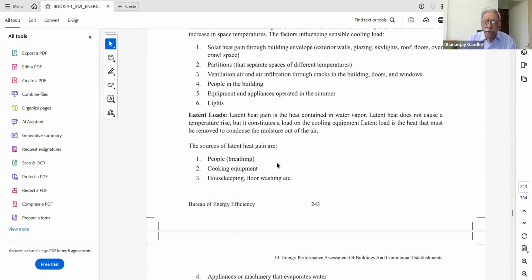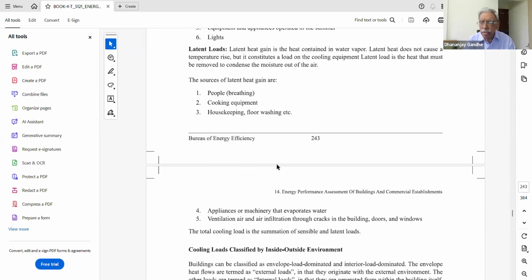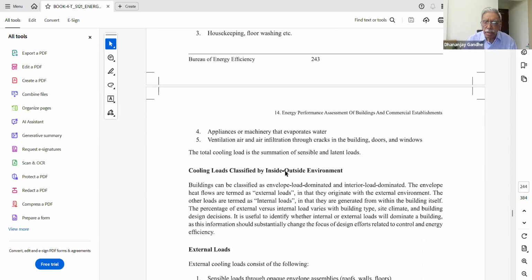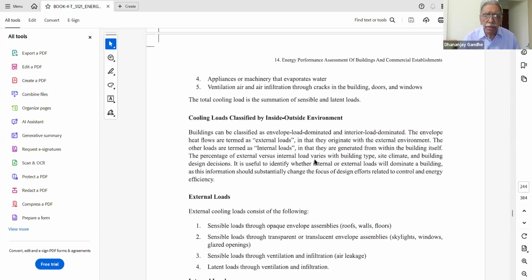The latent heat consists of, again, people: when they breathe, they inhale air, and they also exhale air. So through exhaled air, our breath, when we breathe out, you see the breath is always hot. It is going to add to the heating load. Cooking equipment, housekeeping, floor washing, etc., some operations also contribute to that. Plus, in addition, of course, if you have, let's say, a coffee maker or you're boiling water, the water vapor that goes into the atmosphere also constitutes a latent load. Ventilation air and infiltration air also carry some amount of moisture, so that constitutes latent load. So this is the classification of load.